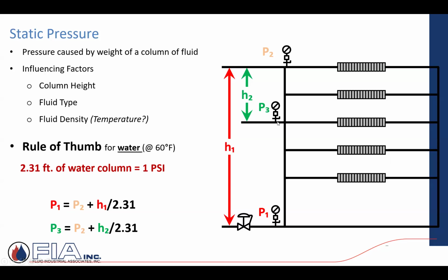As an example, which I don't know how often this would ever happen, halfway through a building from a height standpoint, they'll say, hey, I got a gauge here. It's represented as P3. What is that displaying? Well, again, it would just be the height from where that gauge resides to the highest point. Again, in this case, H2 divided by 2.31 plus, again, that positive pressure, and that's what gauge 3 displays.